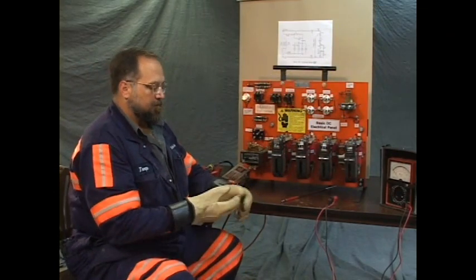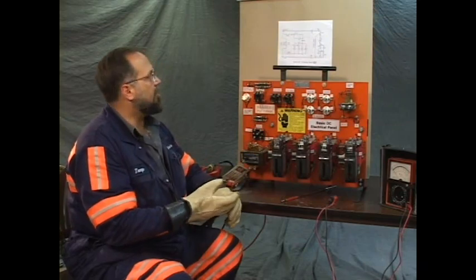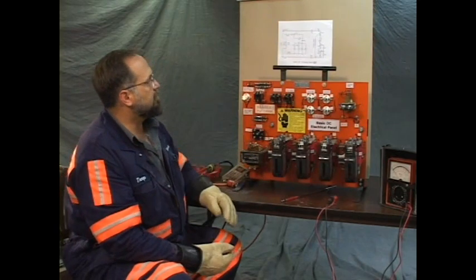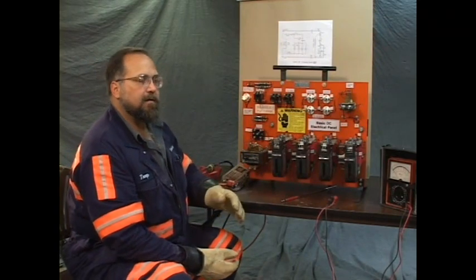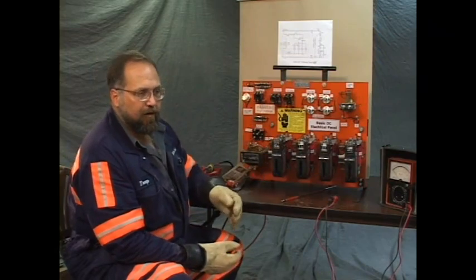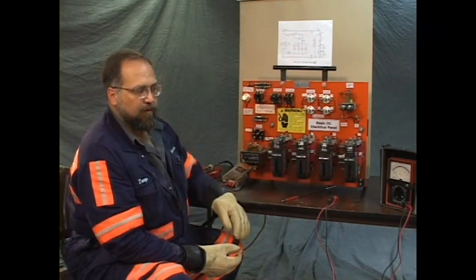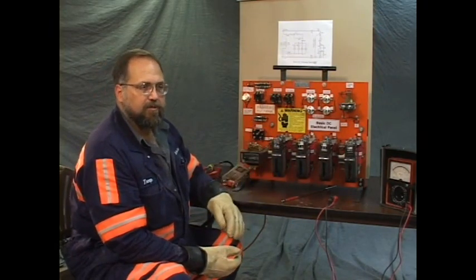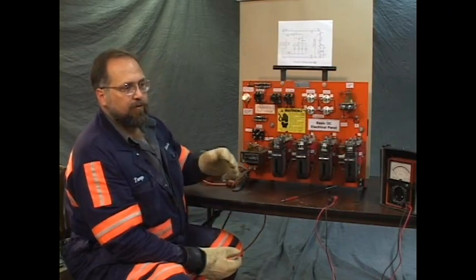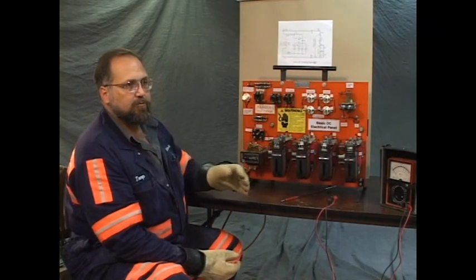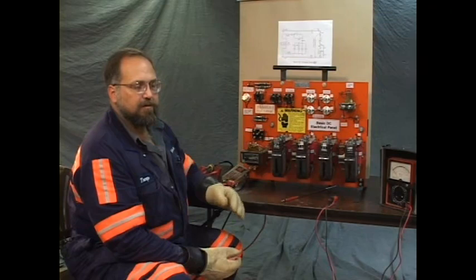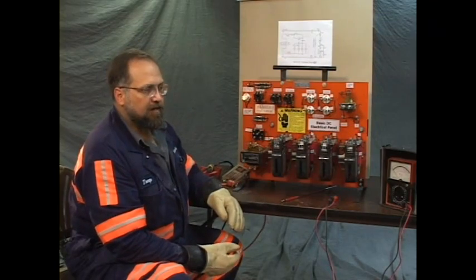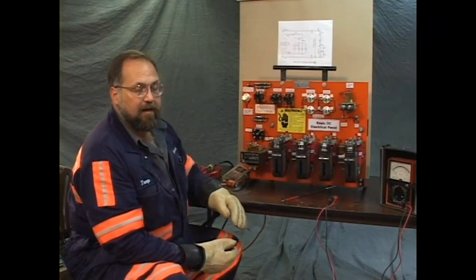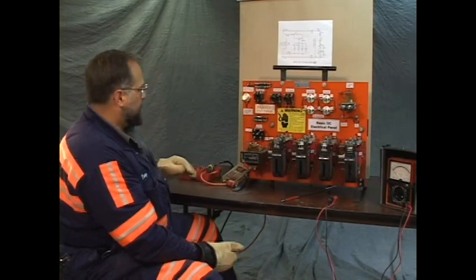Note that as discussed earlier in the problems, we have momentary switches. They're not like switches such as a light switch in your home where you would flip the switch and it would remain in a closed position. These switches return to their normal status as soon as you release them. It's a momentary switch. Let's take the power off and lock and tag, and then test this with the instrument.